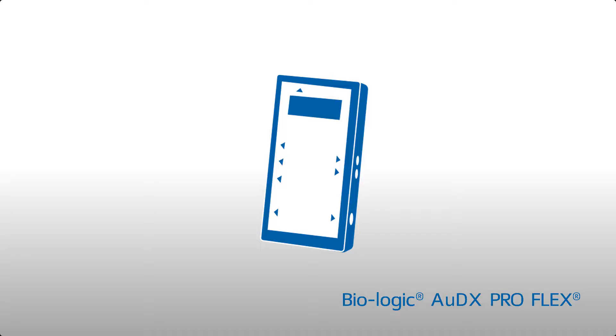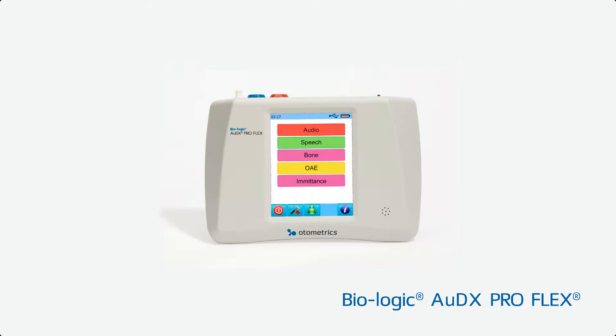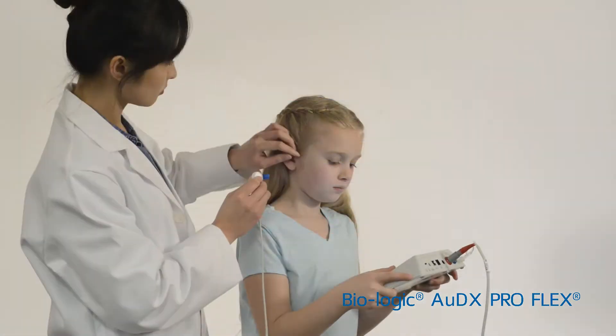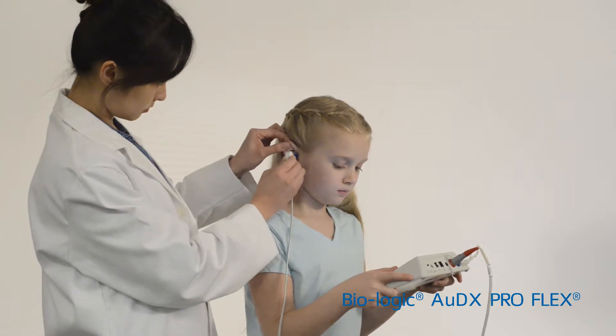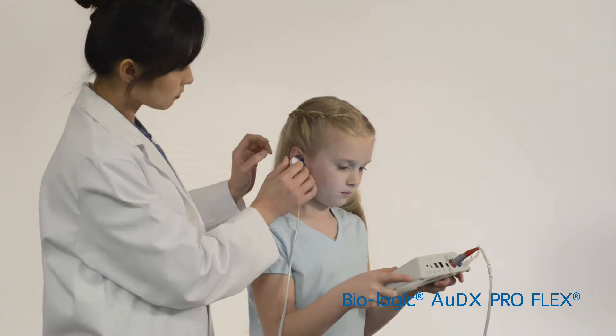The next-generation Bio-logic AuDX PRO FLEX is a flexible tabletop device from Otometrics, offering screening or diagnostic acoustic immittance. Diagnostic test features include multi-frequency probe tones, eustachian tube function testing for both non-intact and intact tympanic membranes, as well as the ability to do pressurized otoacoustic emissions.